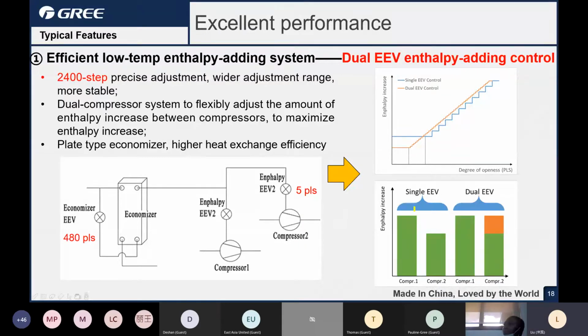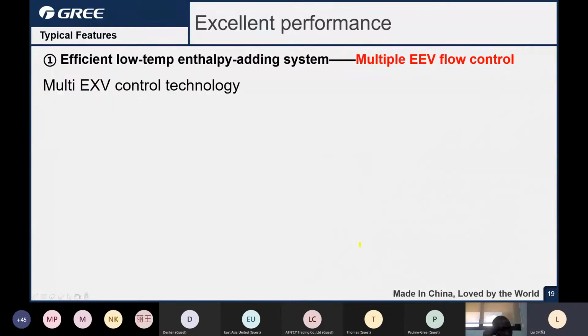Okay, now you can see here, if there is just a single expansion valve and two compressors, for every compressor the enthalpy increase is different. Only one expansion valve cannot do that. So if there are two, compressor 1 and compressor 2 can get the same enthalpy increase, because they can be controlled independently. Okay, that's the advantage of the dual expansion valve. Let's go to the next slide.